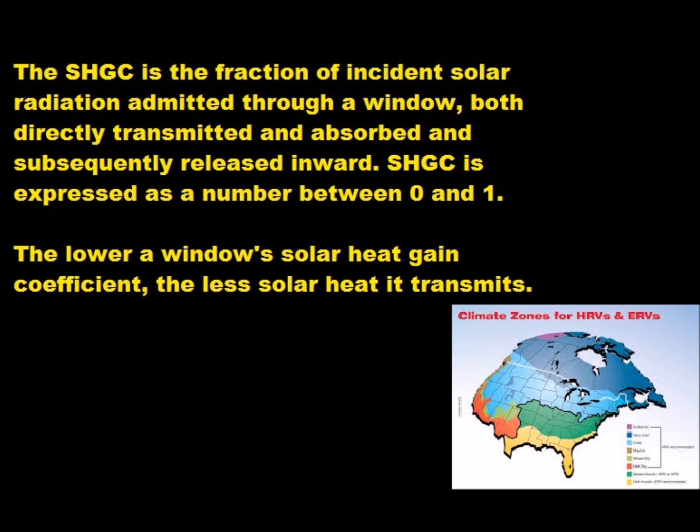Windows on east, west, and north facing walls are reduced in heating climates while still allowing for adequate daylight. East and west facing windows are limited because it is difficult to effectively control the heat and penetrating rays of the sun when it is low in the sky. These windows should have a low SHGC and/or be shaded. North facing windows collect little solar heat, so they are used just to provide useful lighting. Low-E window glazing can help control solar heat gain and loss in heating climates.